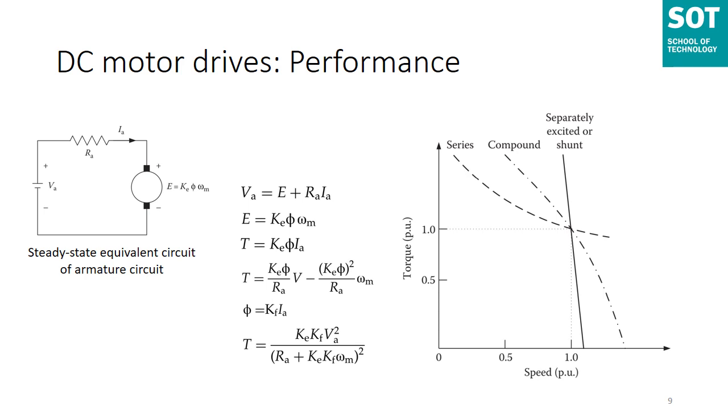The characteristic, therefore, as shown in the dotted line, shows a dramatic drop. A motor of standard design works at the knee point of the magnetization curve at the rated torque. At heavy torque, which is the large current overload condition, the magnetic circuit saturates and the speed torque curve approaches a straight line, as you can see.